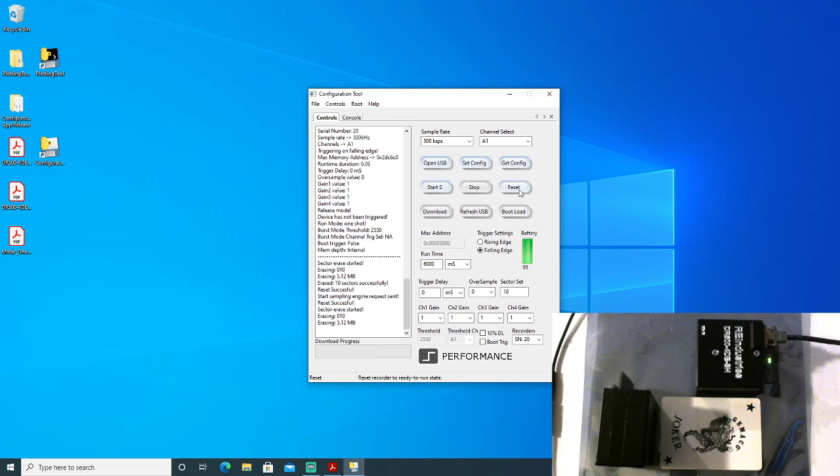And so if we reset to show the function of the stop command in one-shot mode, we just do this again, but instead of letting it run, we will cancel the data acquisition in less than 6 seconds. So while the data recorder is acquiring data and writing to memory, we'll stop this. So we'll start the recorder now. 1, 2, stop the recorder.